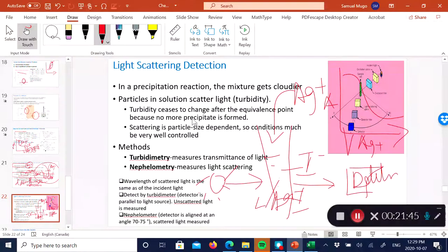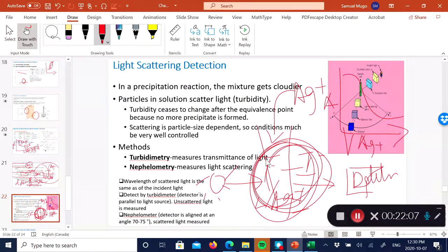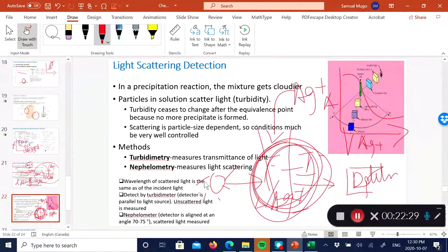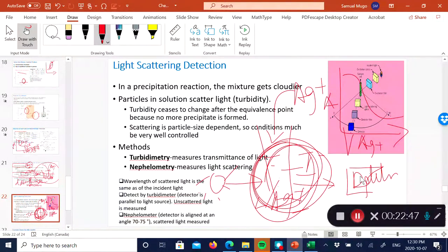There are two spectrophotometric methods for measuring turbidity or dissolved solids. Turbidimetry measures the transmittance of light — the detector is positioned in-line, similar to regular spectrophotometry. Nephelometry measures scattered light — the detector is positioned at an angle relative to the incident light beam. Both are forms of spectrophotometry used when detecting precipitates or dissolved solids.